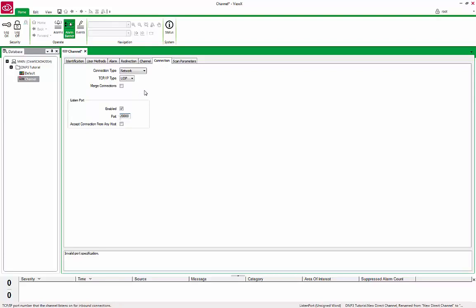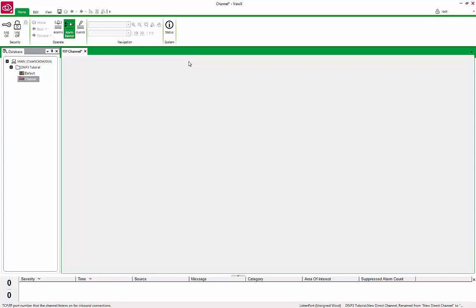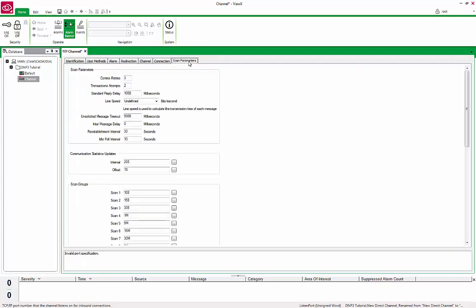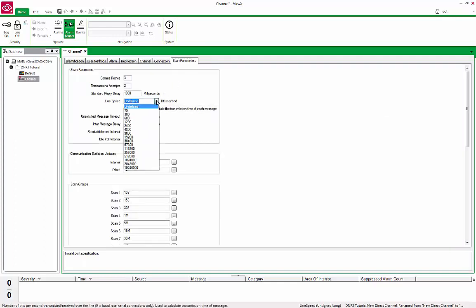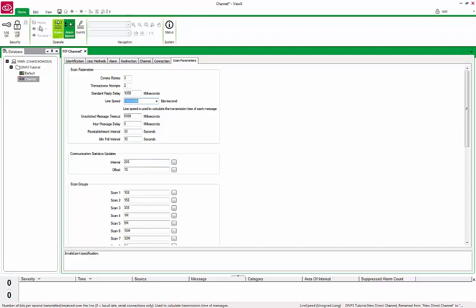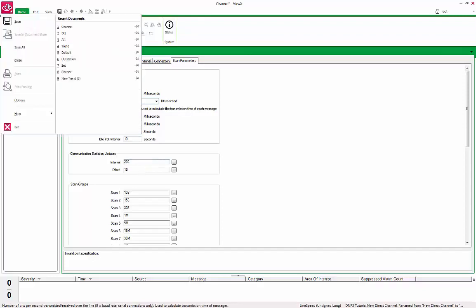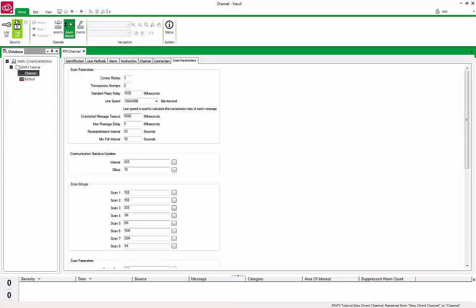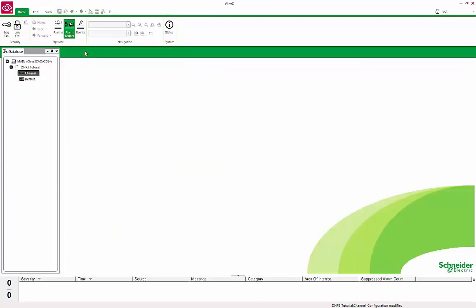This is the port that the remote device will send its messages to the host. Lastly, on the Scan Parameters tab, set the Line Speed to 10,240,000 from the dropdown. ClearSCADA uses this information when calculating response timeouts for communications. Save the channel configuration by clicking on the ClearSCADA icon in the upper left corner or simply click on the Save icon on the toolbar. Close the Properties form.